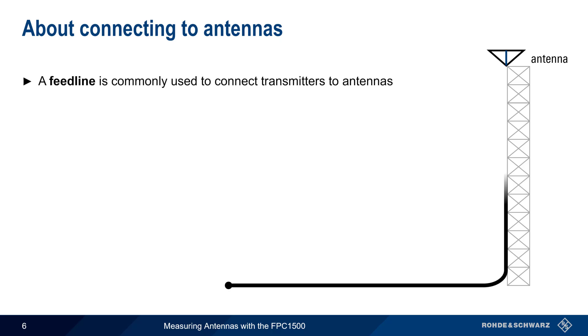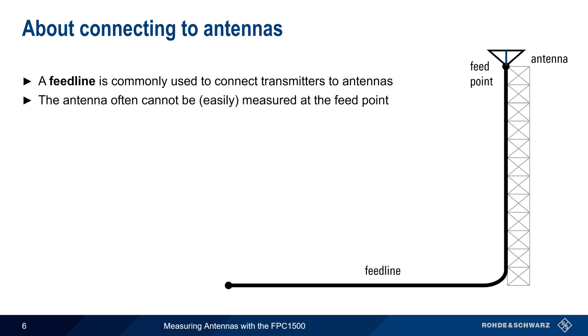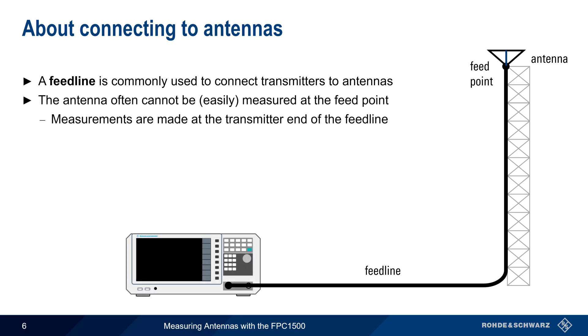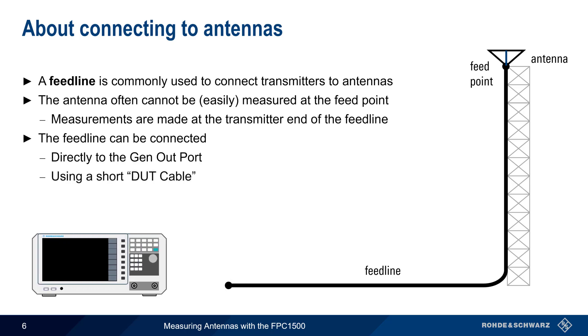In most cases, a feed line is used to connect a transmitter to an antenna, or more precisely to the antenna feed point. Because antennas generally work best when mounted in high or unobstructed locations such as on a tower, the feed point may be very difficult to access, and therefore antenna measurements are often made at the transmitter end of the feed line. There are two methods for connecting a feed line to the FPC-1500: simply connecting the feed line directly to the Gen-Out port, or using a short, high-quality DUT (device under test) cable. This is often done for ease of attachment or to avoid strain on the instrument connector. Measurement accuracy is unaffected by this DUT cable as long as calibration takes this cable into account.